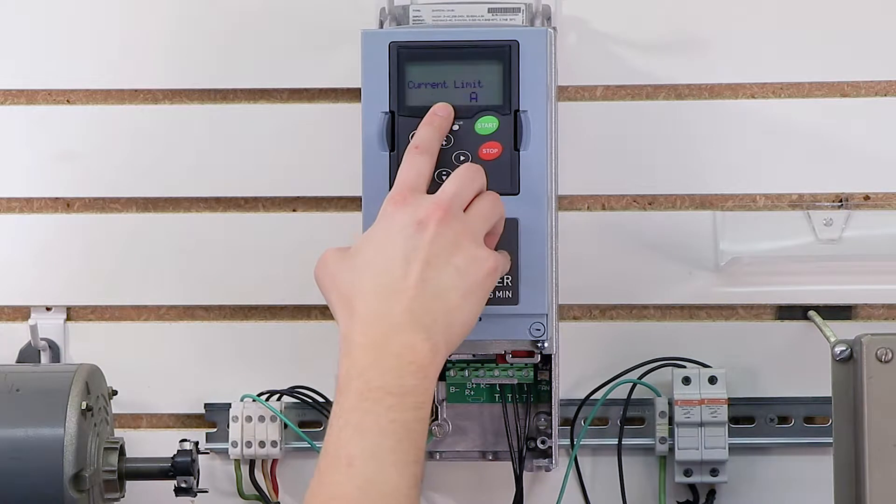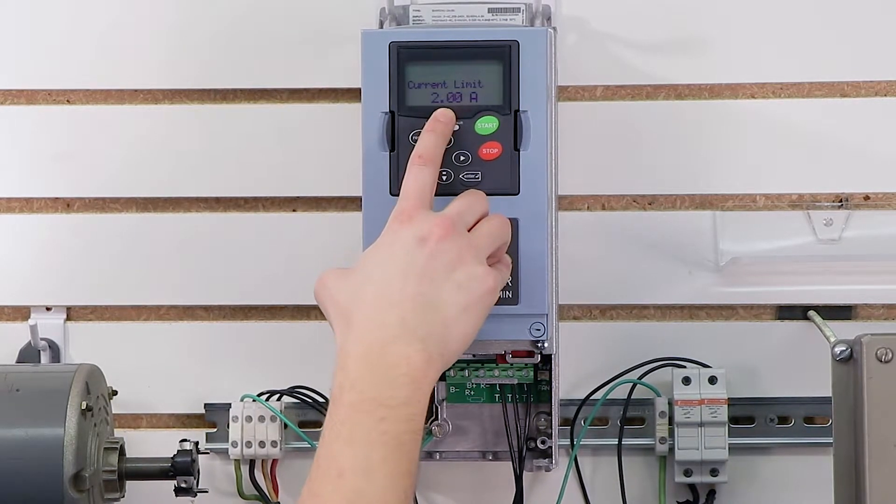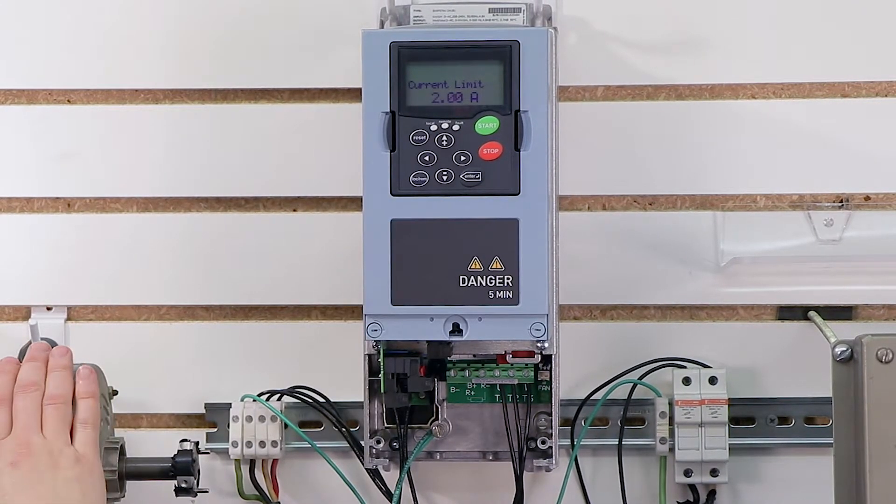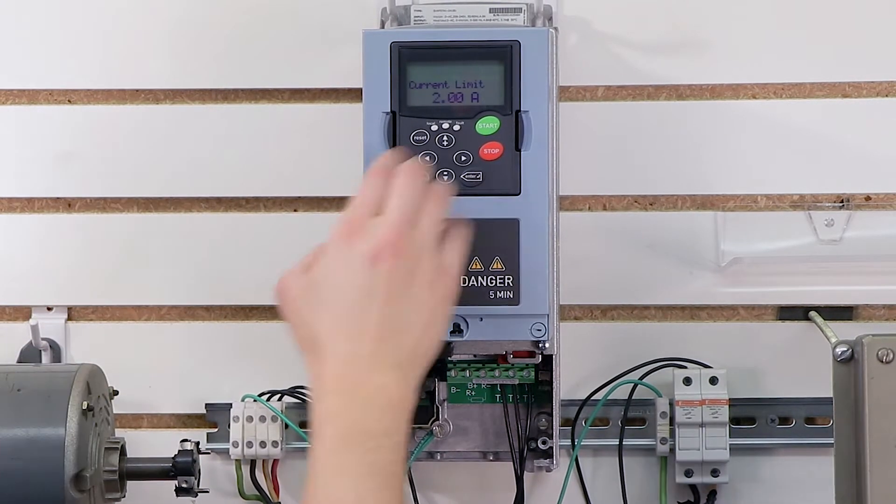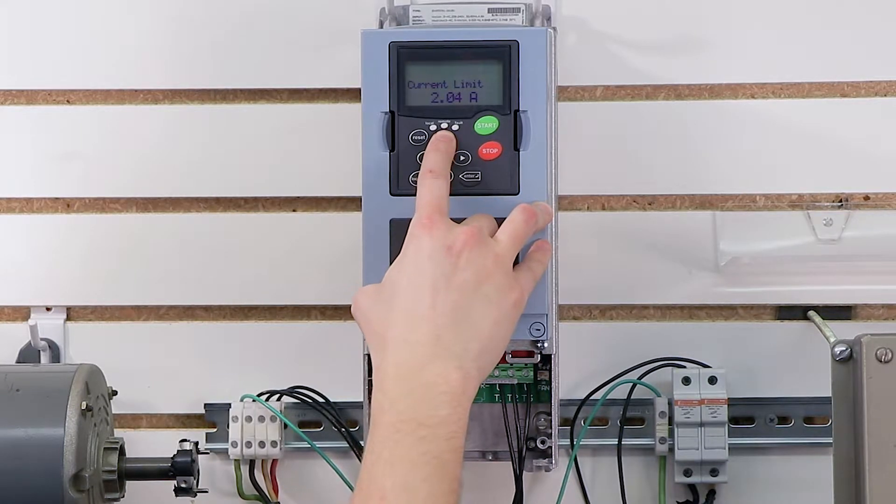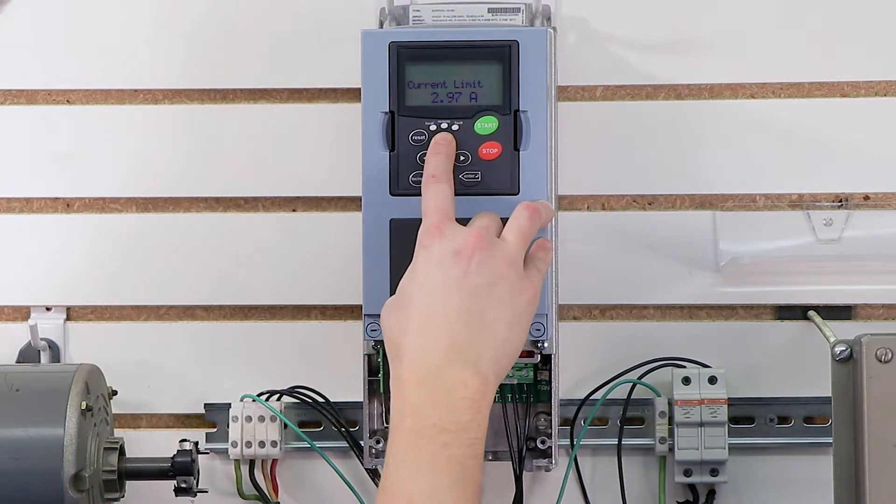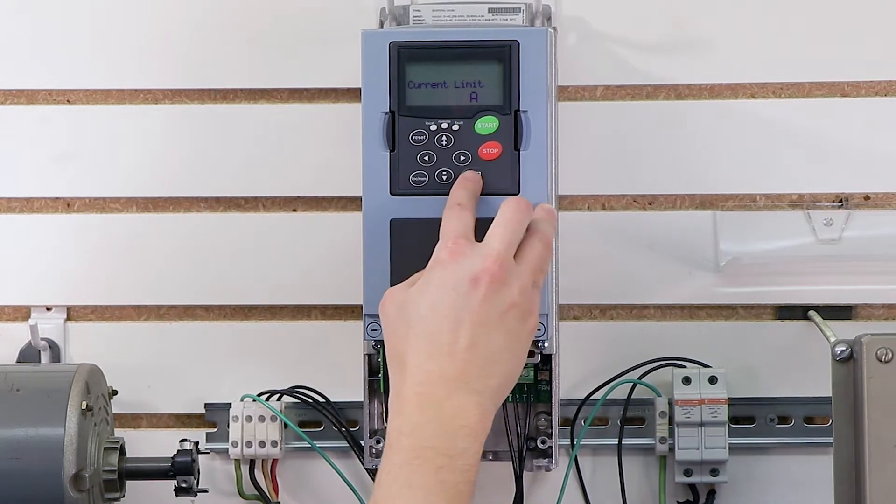Next is my current limit. Current limit is basically going to be on your motor's nameplate. And you're going to take your motor's nameplate and you're going to multiply it by one and a half. So for example, my motor is rated for two amps. But I want my current limit to be 150% of that. So that's actually going to be, if I do the math in my head, I believe it is, yes, it is three amps. So I'm going to hold the up arrow key till I get to three amps. I'm going to press enter.